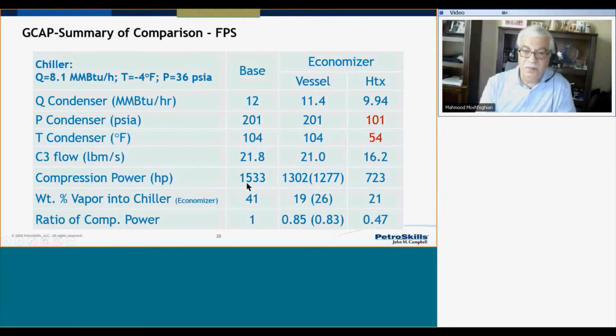Look at the power requirement. The simple refrigeration system has the highest, 1533. With the economizer, with lots of capex and opex, 1302. If I use the optimum, absolute optimum, it's based on geometric average interstage pressure. This is based on equal compression power for the two stages. And our favorite one is 723 horsepower for cooled process gas as a cooling media. By the way, this one requires no extra capex. The same equipment you can use, and it's more effective.